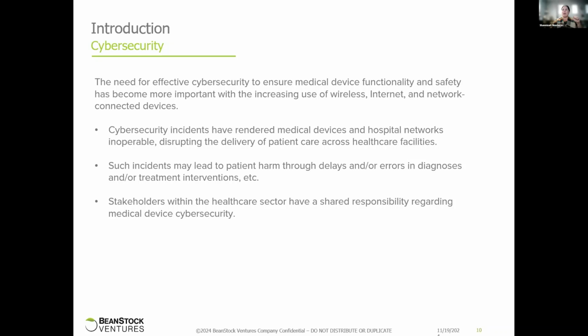FDA came out with new guidance for the pre-market requirements for cyber devices. It impacts any classification you're in. So if you're doing a PMA or 510(k), the cybersecurity guidance will apply. It is quite rigorous. They're enforcing this. There have been a lot of rejections for having old operating systems. So if you're a SiMD product and you're running on a device and it has an embedded operating system, make sure that when you submit, the operating system is current, because the concern is that it's not patchable. The rigor in terms of the technical information that needs to be provided, the bar is quite high. I think that's going to stay for a while.